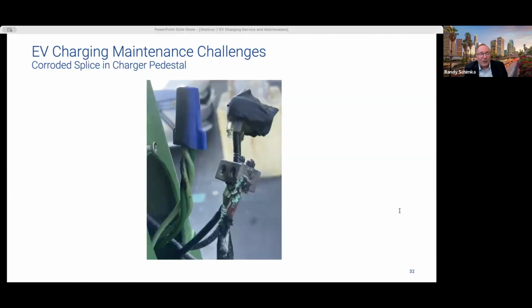This photo shows an open charger pedestal with a hot wire splice that's green with corrosion, all wrapped in black electrical tape. So again, it's a moisture-induced corrosion here that weakens the splice, increasing resistance and fire risk. And electrical tape, it's not really suitable for waterproofing. They make waterproof splices that can be used. So you want to use those. You want to use the weatherproof splice connectors and ensure that pedestals are properly sealed to prevent moisture from getting inside.